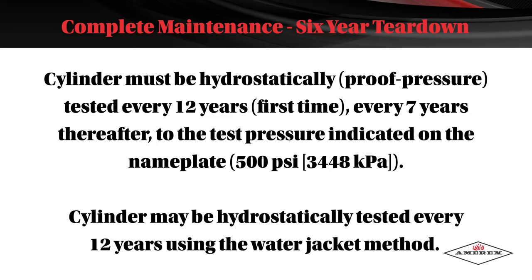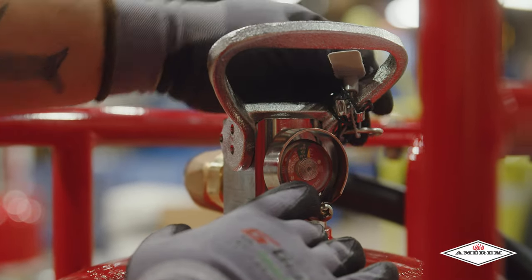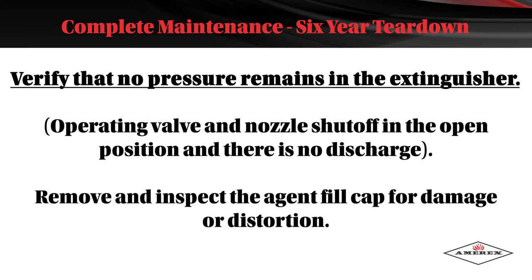The cylinder may be hydrostatically tested every 12 years using the water jacket method. Visually inspect the pressure gauge. If it's bent, damaged, or the wrong gauge, replace it with the proper Amerex gauge. Check the pull pin for freedom of movement; replace if bent or removal appears difficult. Verify that no pressure remains in the extinguisher by opening the valve and nozzle shutoff and making sure there is no discharge.